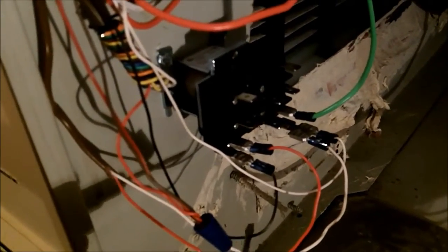Okay, so I've got the humidifier wires hooked up. Black comes back from the humidistat and feeds the coil of the relay. And when it feeds the coil of the relay, of course it energizes. It's going to send power to those terminals where it needs to send power to. But this black wire here, that is the humidistat. The red wire is the humidifier. So when the humidistat sends power, it's going to energize the humidifier. The white wires, of course, are the commons. This one's coming back from the humidistat. This one's going to the humidifier. I just got them.